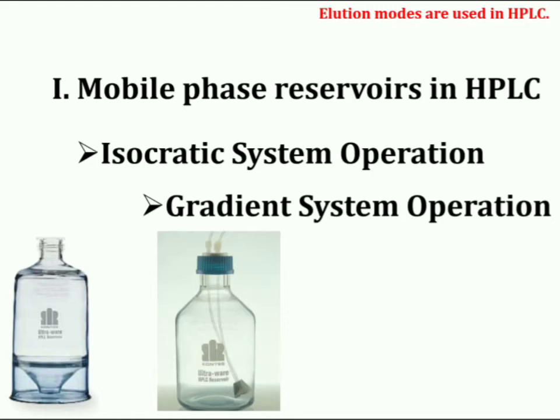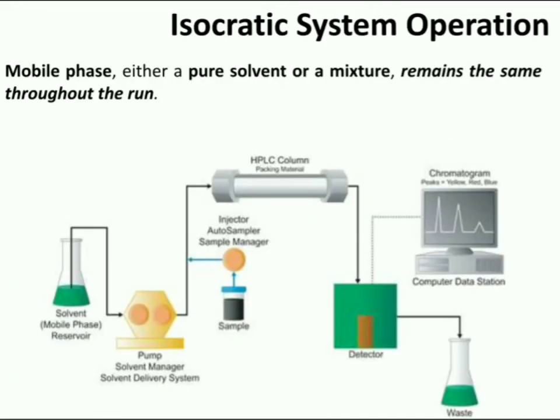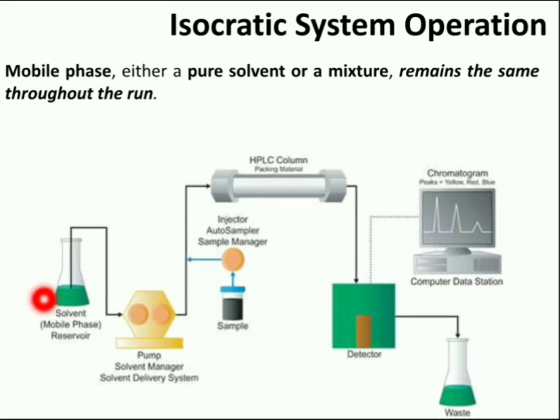Generally two types of techniques are used for handling the mobile phase: first, isocratic system operation, and second, gradient technique. Isocratic means that the mixture of your mobile phase is consistent over the complete testing time — the mobile phase, either a pure solvent or a mixture, remains the same throughout the run.